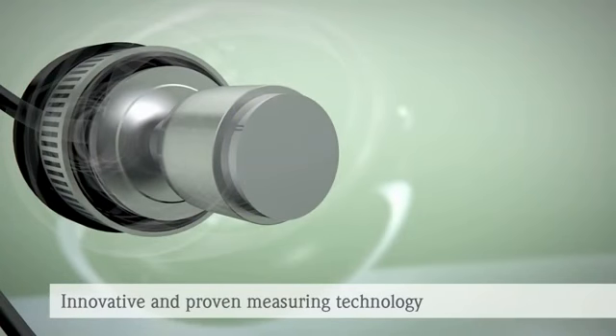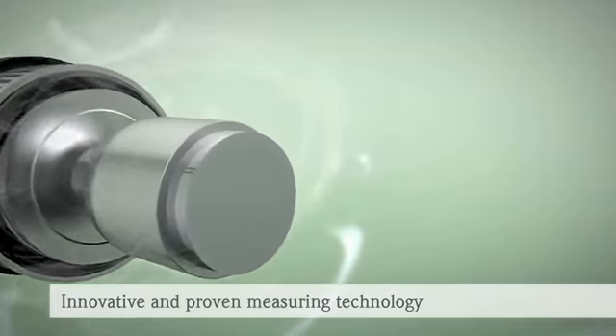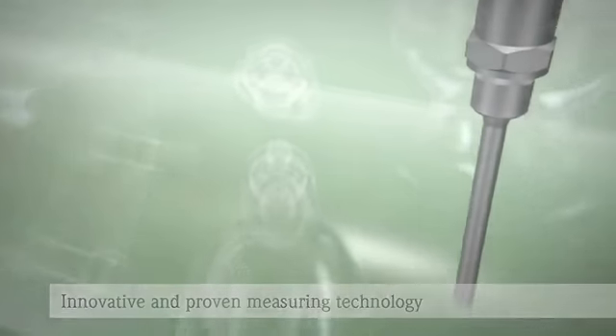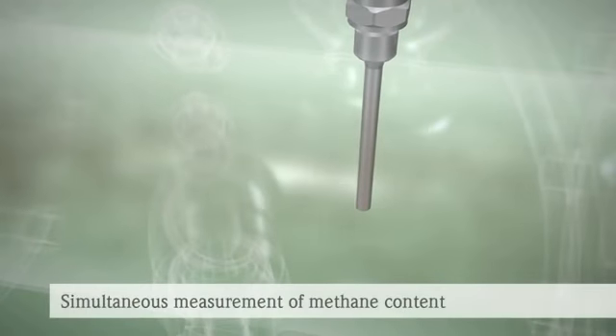Nevertheless, the speed of sound measured directly indicates the gas composition. This fact, along with the built-in temperature sensor, enables the Prosonic Flow to determine the actual methane content of the gas continuously.